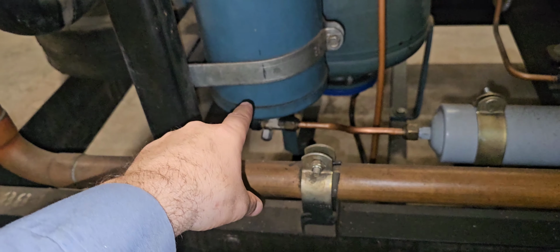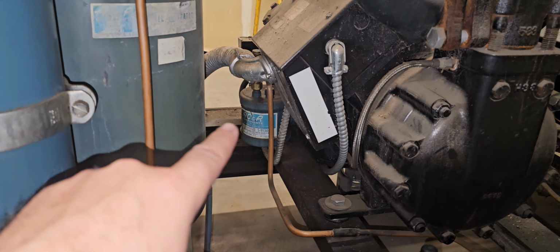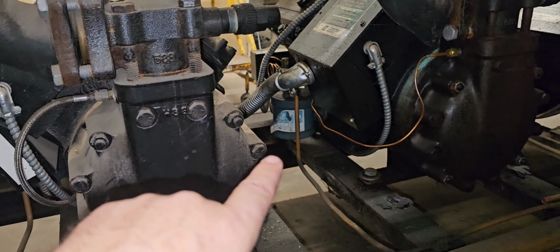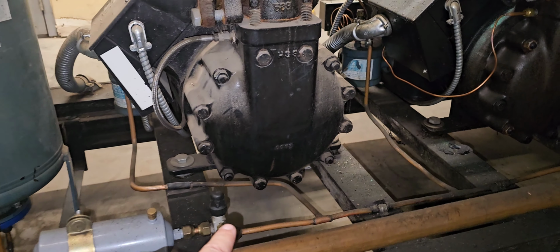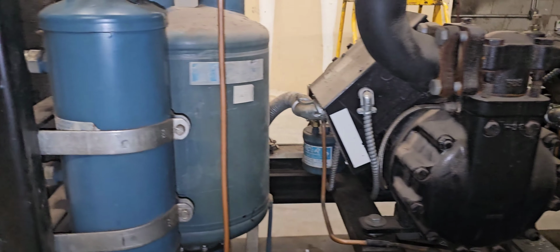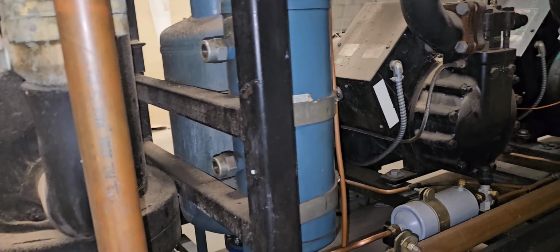And then it's simple. All it does is it comes through, and as compressors need oil, it goes into our pots. As our floats call for oil, that oil is going to come out of the reservoir, through that filter, into that line, and it's going to go where it's needed. So pretty simple. And then you can see we have sight glasses on these reservoirs.